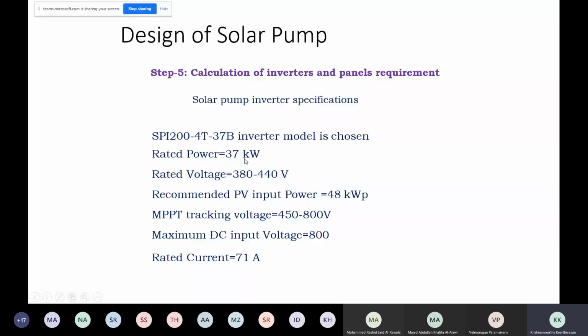We will never match the load power exactly. If the house is 2.8 kilowatt, we will not go for exactly 2.8. We will multiply it by 1.25 and make it 3.2, I think. 25% extra we go for safety purposes. None of the voltage ratings or current ratings should affect the setup. And then MPPT tracking voltage, maximum DC input voltage. And to calculate, the power divided by voltage will give you the current: 71 amps.